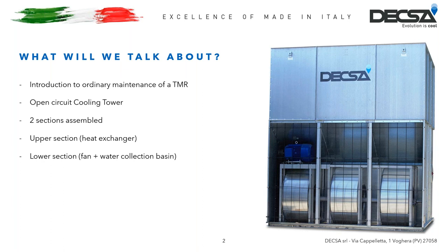The remaining period can be used to carry out all checks and extraordinary maintenance. If the tower is part of an industrial plant operating 12 months per year, a few consecutive days of downtime are usually expected for maintenance activities. I think it's good to organize a few more hours outside the expected downtime, because some periodic activities require more than just one annual intervention. For example, greasing of the bearings must be carried out every four months or 3,000 operating hours. Same goes for the control of the belts. These activities take about an hour per unit, and in the meantime the inlet water system can remain operating.